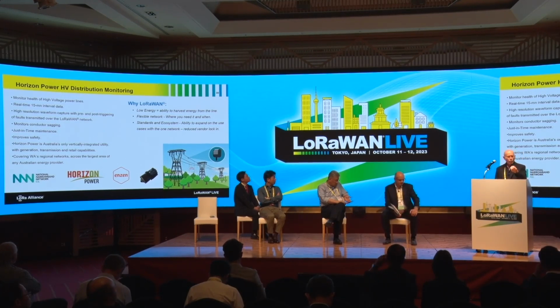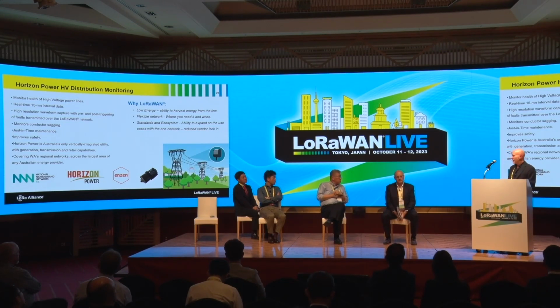And of course, all of this is done by harvesting the power from the line itself. So it's a Class C, actually, this particular device is a hybrid Class C, Class A device, but it leverages the harvesting power from the transmission line, so there's no need for a battery. It's got a little solar panel built into the device to increase coverage if the power in the line is quite low, and in some cases in remote locations that can happen quite often, and therefore provides the utility with the ability to understand the quality of the power, whether they have a line down situation or whether indeed they've got a sagging line, all in the one device and empowered all by LoRaWAN.